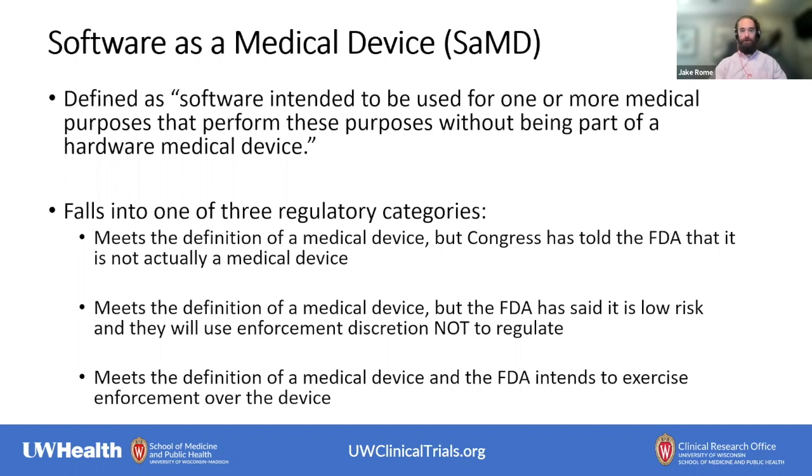So I just want to address a few devices that fall in this gray area that are showing up more and more frequently based on where research is at right now in the United States. So one set of devices in general that falls into this gray area is software as a medical device, or SAMD. So this is software that's intended to be used for one or more medical purposes without actually being part of a hardware. So when you think about an MRI machine, the MRI machine includes both that hardware and the software and its approval. So they wouldn't consider that MRI software, which is part of the device, to be SAMD. This is really independent software that acts as its own device.